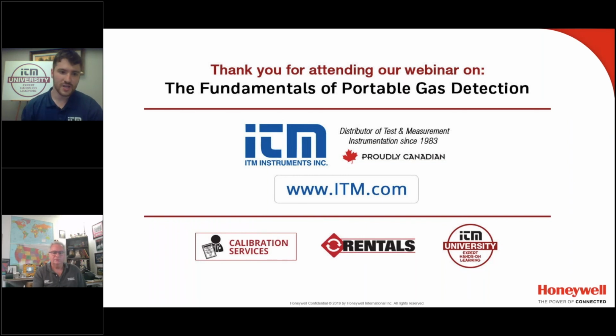Jamin asked, what is the difference between zero gas and oxygen 20.8%? Zero gas is typically like if you were calibrating a carbon dioxide meter. In fresh air, there's about 400 ppm carbon dioxide. So if you need to do zero air, sometimes we recommend using nitrogen so you know it's not a real world situation, since fresh air will have at least 400 ppm, or indoors could be upwards of 1,000 ppm. So you just zero that out. For most of our monitors, you just need fresh air. If you have a docking station with no cylinder hooked up, that's fine, but if you're calibrating a CO2 meter on a docking station, you would use zero air or nitrogen.